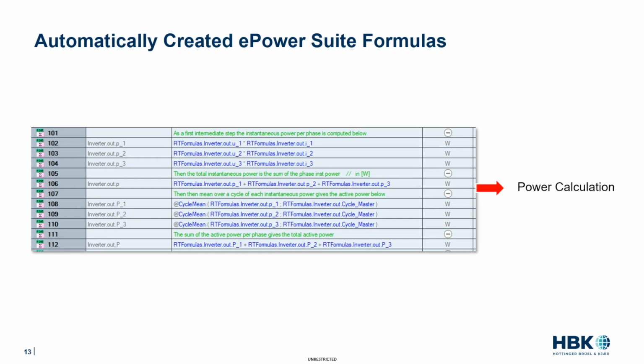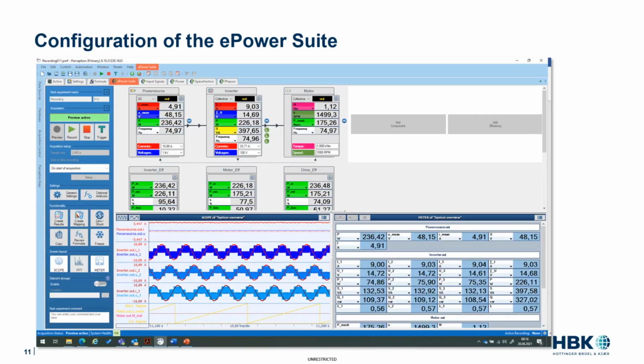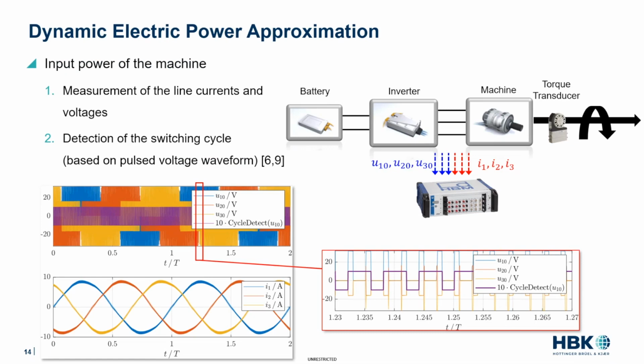Now I'll move on to today's special topic: dynamic power approximation. We start with the same topology as before and take the same measurement—the three voltages and three currents at the input or output of the inverter or input of the machine. But instead of calculating based on the fundamental cycle of one of the currents, we now calculate the switching cycle—the switching frequency of the frequency inverter—by applying a powerful detection algorithm on the inverter output voltage, resulting in the switching cycle.